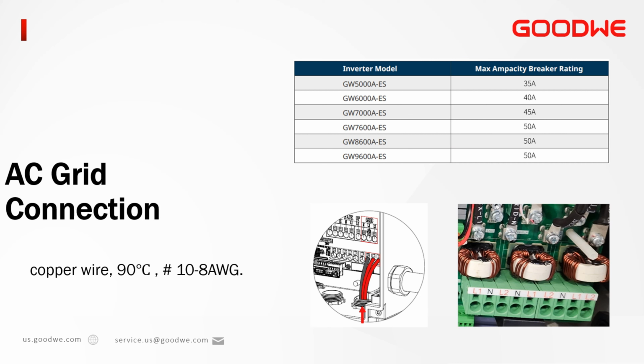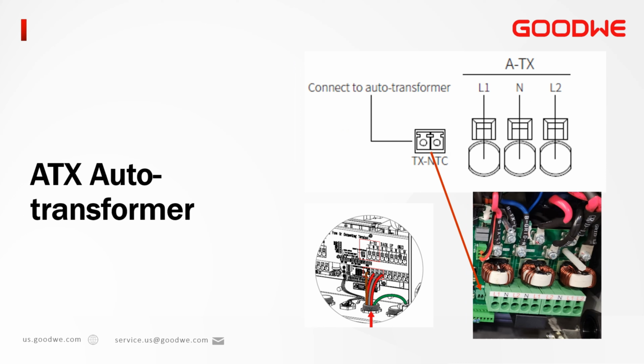Since we are talking about the AC side, it is worth mentioning that this inverter series was designed to connect to 120 to 240 volts with a neutral, each phase at 180 degrees. The UL version inverters can adjust voltage and frequency as needed. Please refer to the installation manual for more information. The ATX, or auto transformer, is required if you are going to use this inverter series to back up loads during a power outage. Do not attempt to operate AES or AVP without ATX. The ATX has its own enclosure and is in most cases installed right under the inverter.